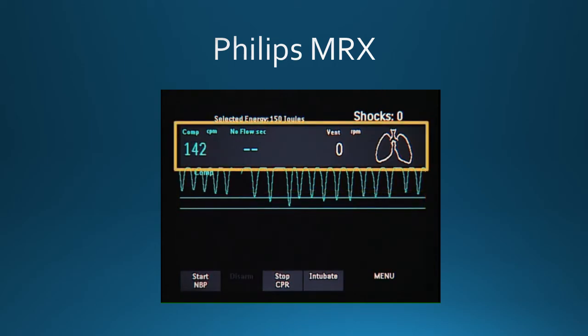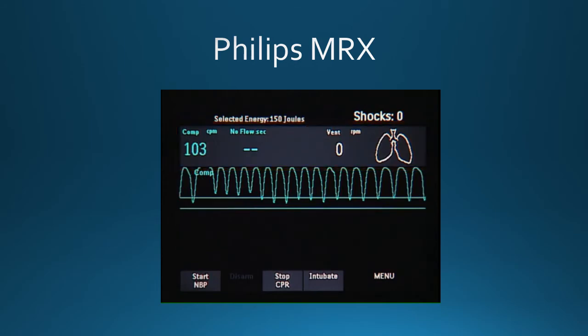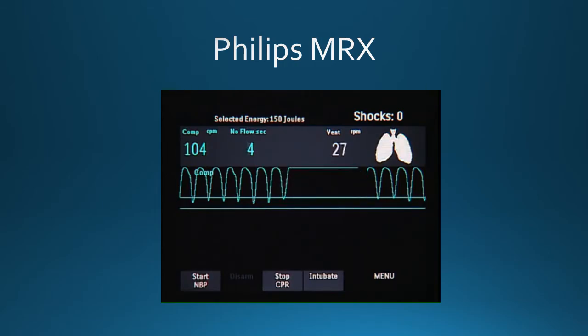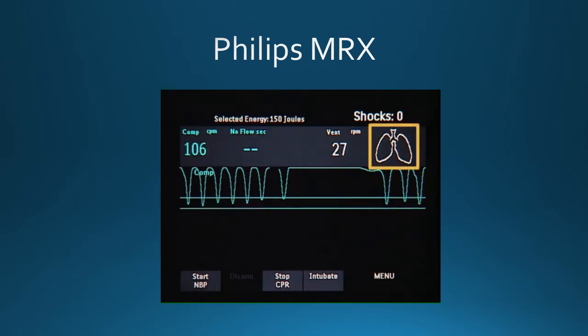This area contains the numeric values for compression rate, no flow time, and ventilation rate, and a ventilation volume icon. The compression and ventilation rates are a moving average rate measured per minute. The no flow time indicates no CPR activity beginning at 2 seconds and incremented with each additional second of inactivity. The ventilation volume icon depicts the approximate level of ventilation volume. There are 4 states of volume: empty, 1/3 full, 2/3 full, and full. If ventilation cannot be measured, lungs marked with a question mark appear.